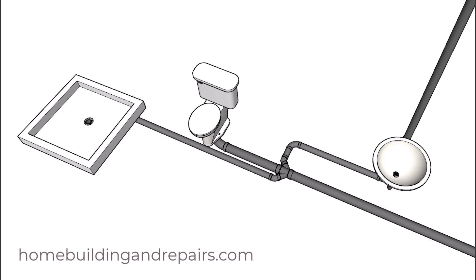Now the last thing I want to mention, if you didn't catch it in the video, is that all we need to do to increase the slope in the double Y fixture is to increase the slope in the drain pipe that's going from the toilet through the double Y and then down to the 90 that turns and then goes down the wall. So that would be a simple fix to this situation if we had the room.